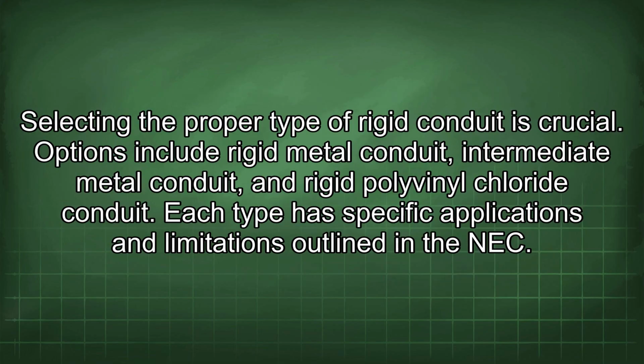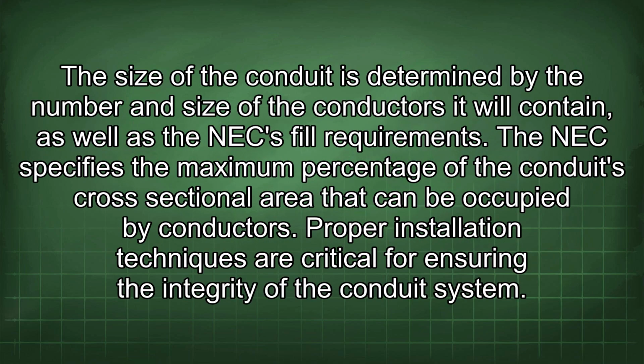Selecting the proper type of rigid conduit is crucial. Options include rigid metal conduit, intermediate metal conduit, and rigid polyvinyl chloride conduit. Each type has specific applications and limitations outlined in the NEC. The size of the conduit is determined by the number and size of the conductors it will contain, as well as the NEC fill requirements. The NEC specifies the maximum percentage of the conduit's cross-sectional area that can be occupied by conductors.